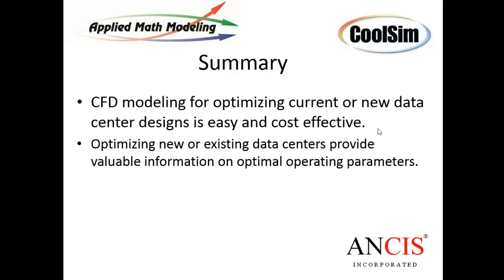Yes. We're modeling the flow inside the ducts, and so you saw in the first model that Dana had stepped the duct down in size, and we do full CFD calculation inside the duct, and so those sizes do change the velocities and the pressures inside the duct. So yes, if you have a duct header and you disable different AHUs, air handlers, the model will show how those ducts flow data. So yeah, it's fully accurate with respect to modeling in the interior of ducts. And it does it quite nicely.